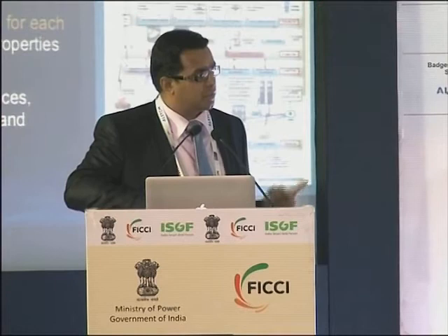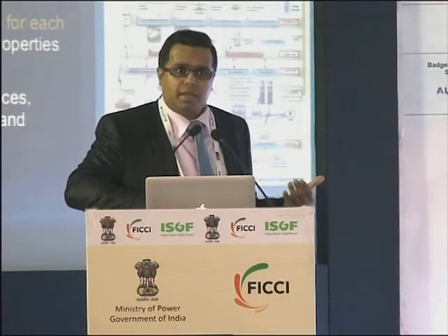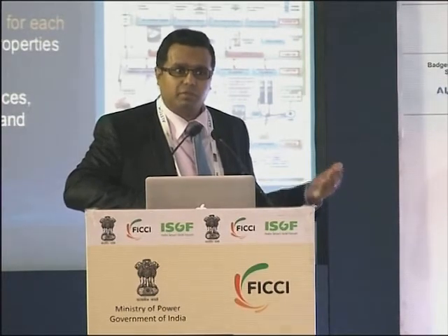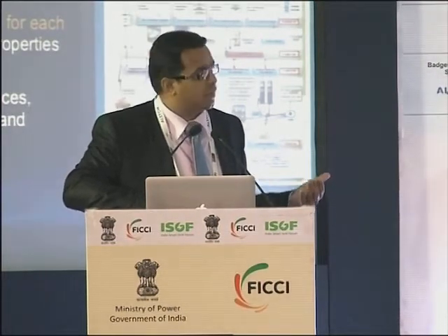For example, in substation, there are low latency applications: 4 milliseconds delay, 10 milliseconds delay for teleprotection. How do we achieve that? In AMI, we have different layers of bandwidth, security and delay requirements. At DA, we have another set of requirements. So before we invest or plan something to put together, it's critical to have some kind of reference model. And it's not about products here. We are not talking about products.